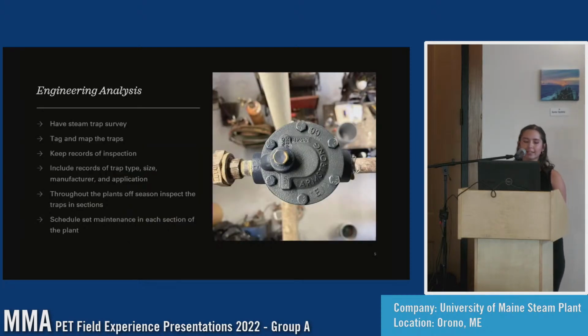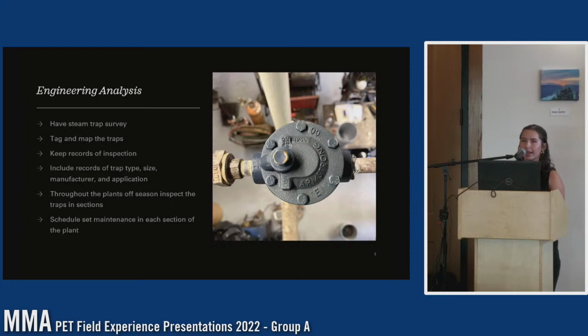My engineering analysis is to propose to first have them come in and analyze all of the steam traps and survey them, tag and map everything so we can keep track and we know when we've inspected them, trap size, trap type, manufacturer, and application. And I propose to do this around our plant's off season, which is in the summer. And because UMO doesn't have a huge budget for this, I would suggest to do it in sections, and it would be very cost effective for us. If only 10 were fixed, we would still be saving enough money to make the maintenance worth it.